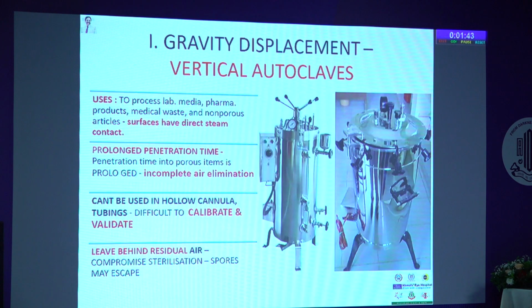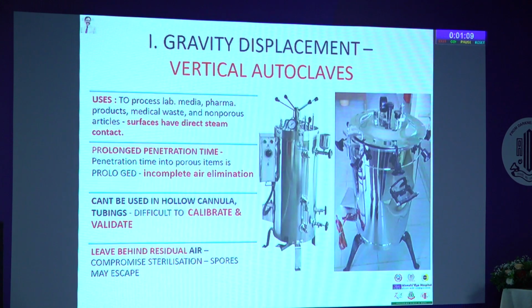So let's go to the main topic, the pros and cons of various autoclaves. This is the commonest autoclave we see in many of the hospitals. So basically it is a lab autoclave, and one important principle is surfaces have to have direct steam contact for efficient sterilization. This is the reason that whenever NABH or any regulatory organization visits or inspects a hospital, we look for what all you sterilize in this. Right? If they are using it to sterilize reusable cannulas or reusable tubings or vitrectomy tubings, we ask them to switch over to a good quality Class B autoclave.